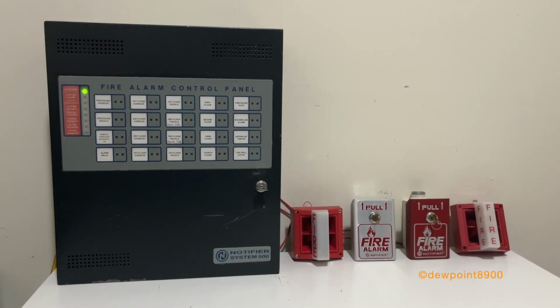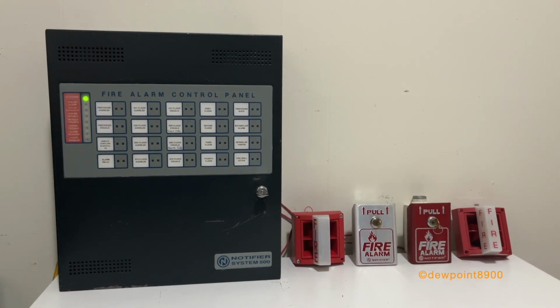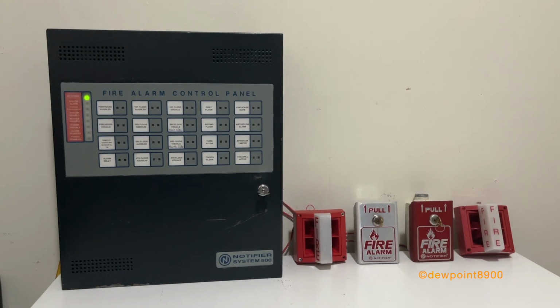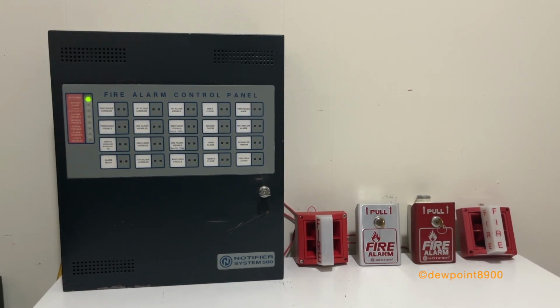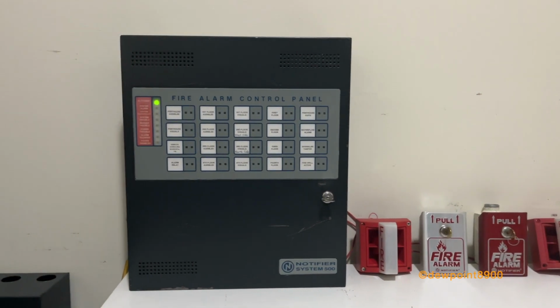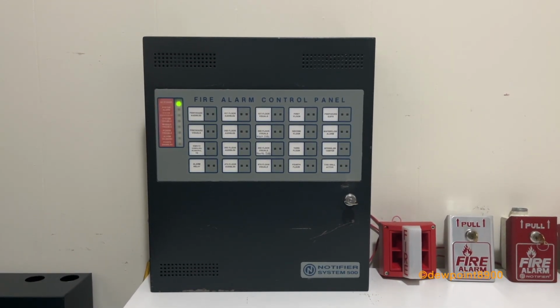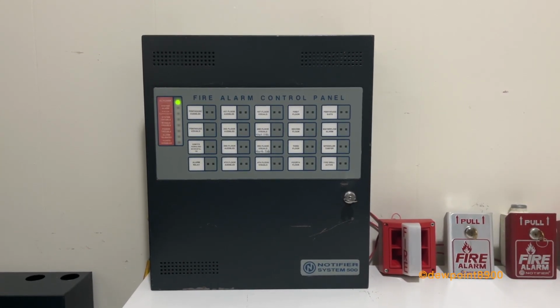Selective signaling is more common in high-rise buildings where you may not want to evacuate everyone in the building for an alarm condition. Instead, you'll just evacuate people in the alarm floor and the floors above and below, and maybe a few additional floors depending on the evacuation procedure. Of course, the System 500 was not designed for high-rise buildings, but this is a good demonstration of the I/O mapping capabilities that this and the System 5000 had.